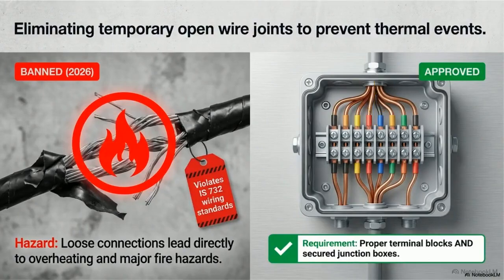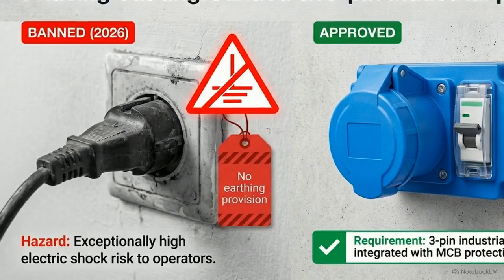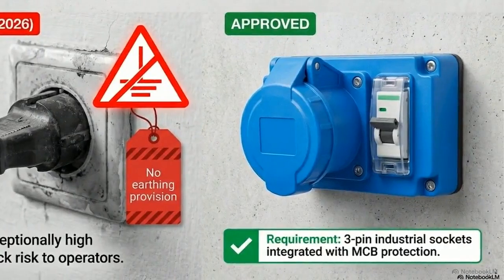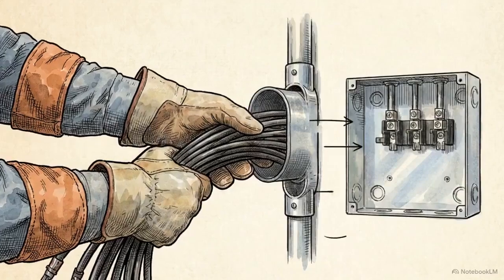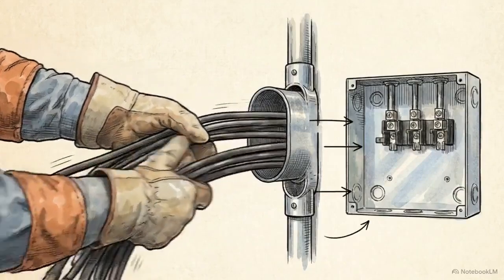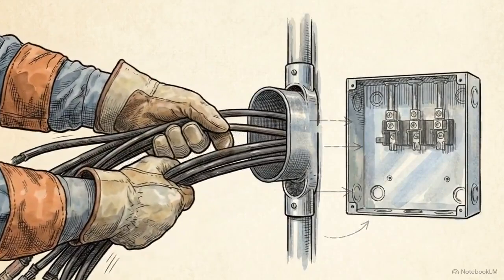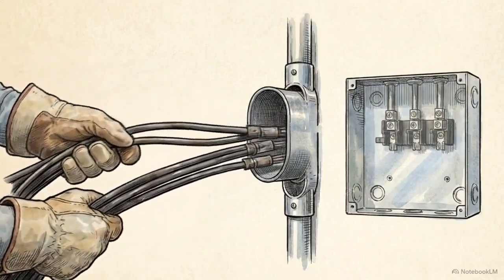We are phasing out the 2-pin plugs pictured left. Without an earthing provision, operators face an exceptionally high risk of electric shock. The new requirement on the right is a heavy-duty 3-pin industrial socket, equipped with an integrated MCB right at the connection. All makeshift wiring and ungrounded connections have to be permanently ripped out and replaced with engineered enclosures to stop thermal events before they can start.